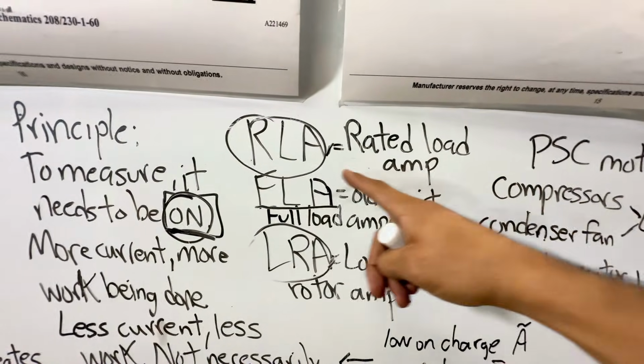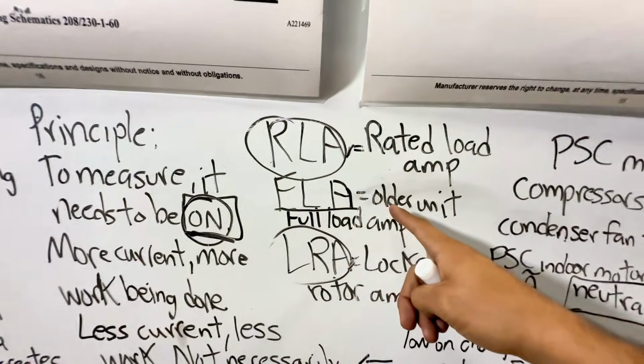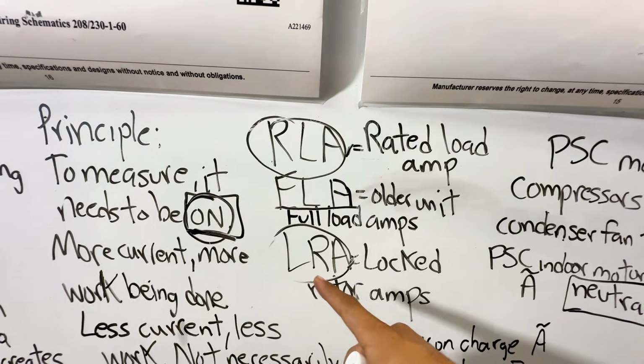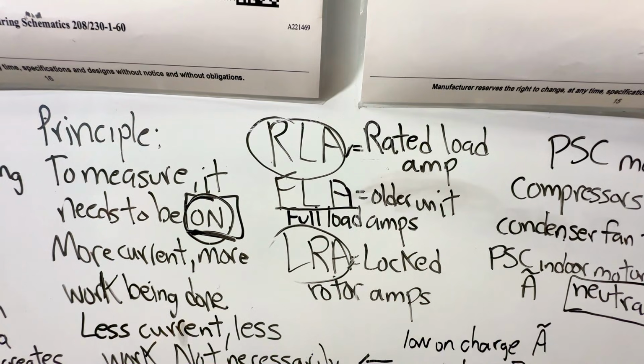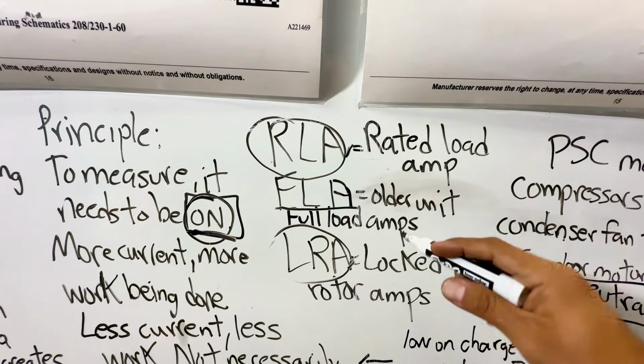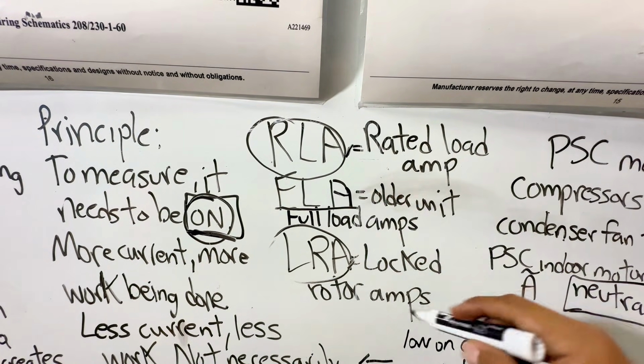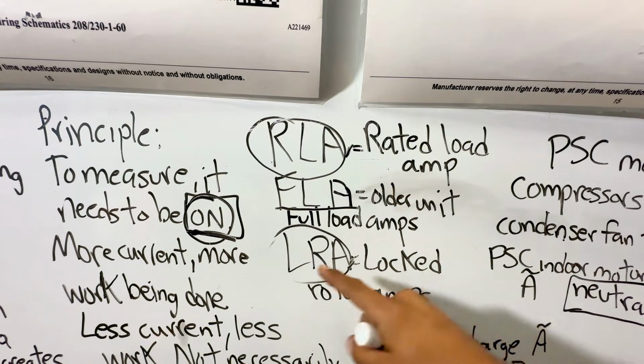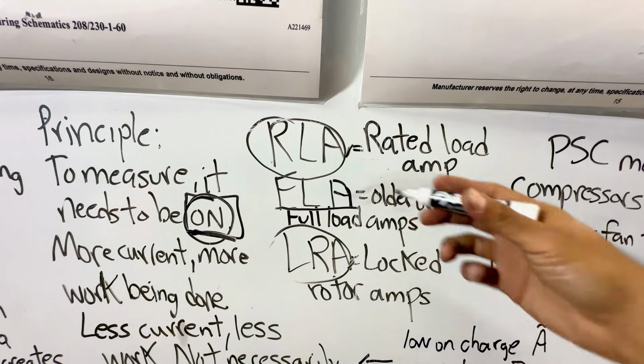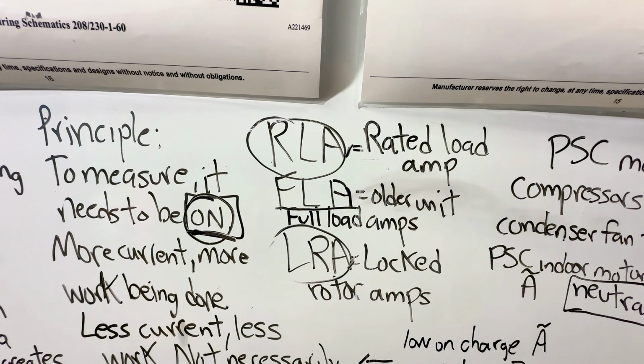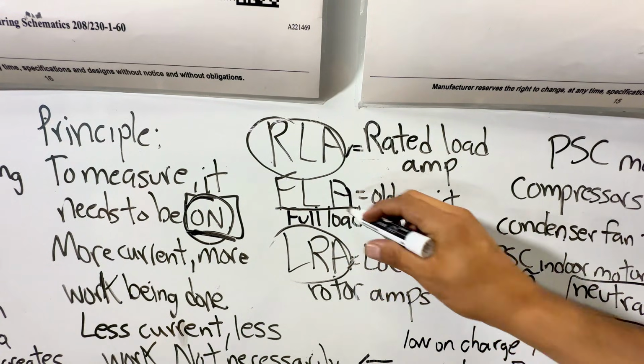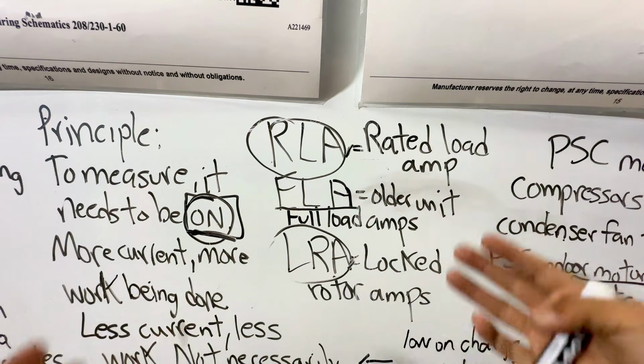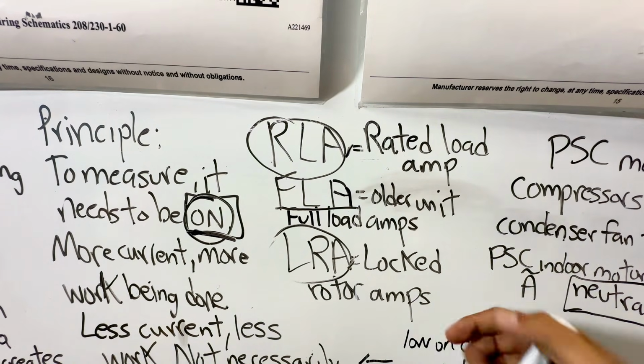Rated load amps, RLA, full load amps, and then LRA, locked rotor amps. So back in the day, compressors would use full load amps and locked rotor amps. So this hasn't changed, and I'll show you an example of that. But compressors, I think before 1976, I forgot the year, they would use full load amps on compressors. But all the compressors that you see today, they use rated load amps, okay?